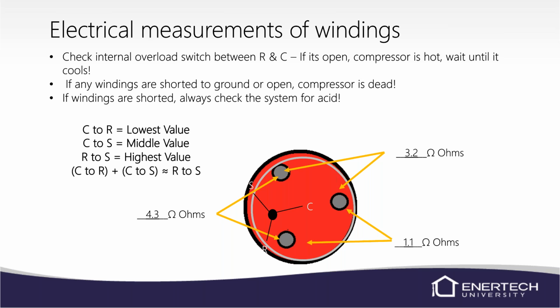You'll do common to run, common to start, and run to start. So common to run should be your lowest value. You can see in this picture here, we've got 1.1 ohms. The common to start should be your middle value, which we're showing here at 3.2. And then run to start is your highest resistance value. We've got it here at 4.3.